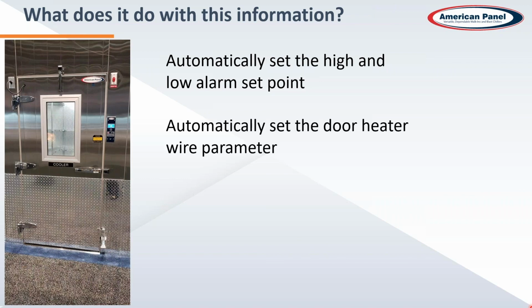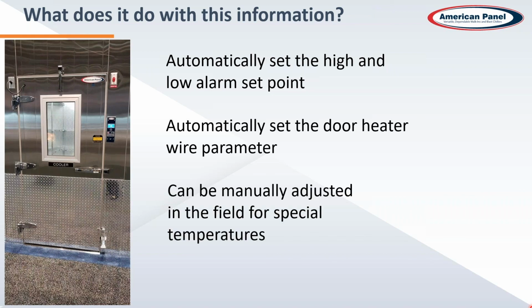It will also automatically set the door heater wire parameters to keep that door frost and condensation free. In addition, the unit can be manually adjusted in the field for special temperatures. In case you have maybe a wine room or a special environmental room, scientific room that's at a different temperature, you don't want the alarm constantly going off. So you do have the option to go in and manually adjust the temperature alarm high and low settings.